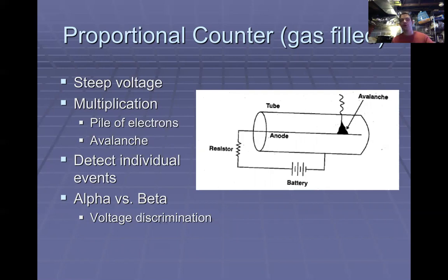So those will go their respective directions, and if they go with enough force, they will collide with other molecules in that volume and actually ionize those, creating that avalanche effect. Now, in a proportional counter, it is a proportional avalanche. It is not a full-scale ionize everything avalanche. That's what happens with GMs, which we'll get to. For this, it is a very calculated multiplication factor.